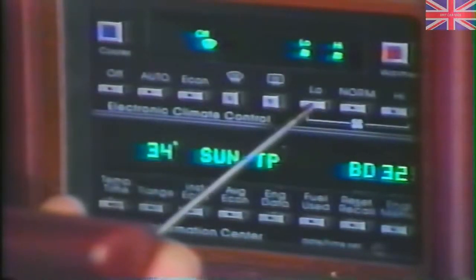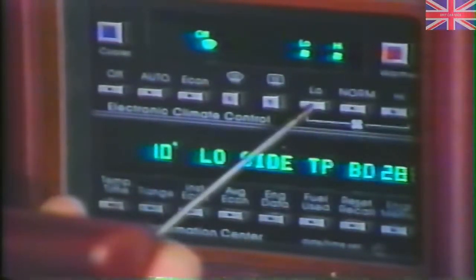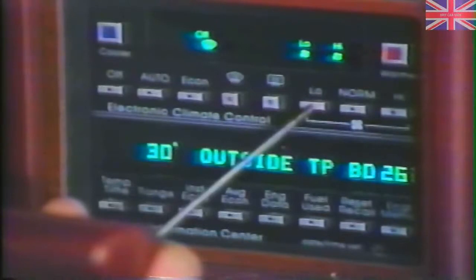As you can see, with the malfunction repaired, we have a 10-degree low side TP. 10 degrees? Yes, all temperature and pressure readings are displayed in centigrade or kilopascals.